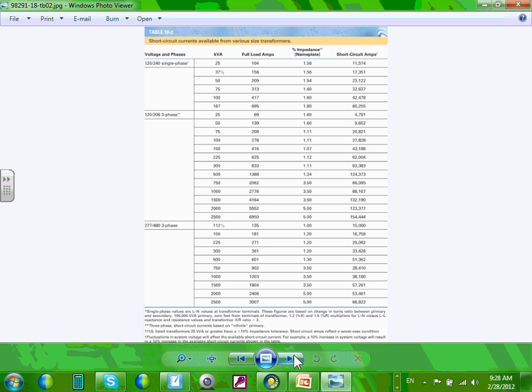Okay, can you guys do me a favor? It's a 300 kVA transformer, so if your transformer is 250, this table is worthless. Does that make sense? If you look at zero distance from the transformer, if I'm using a 3-aught, can you see the number is the same for all of them? It doesn't matter, right? At zero distance, the impedance doesn't matter.